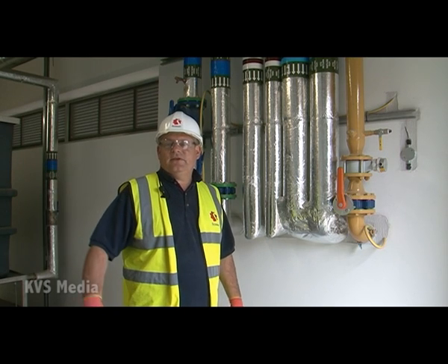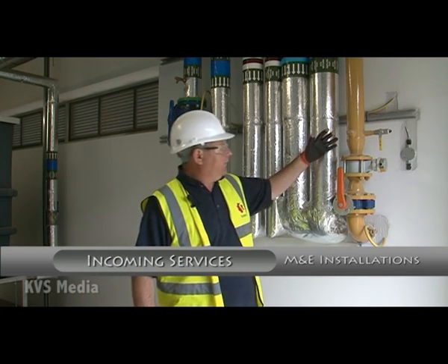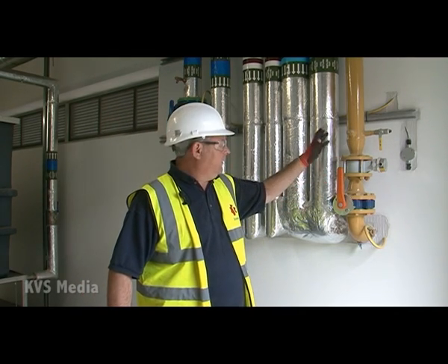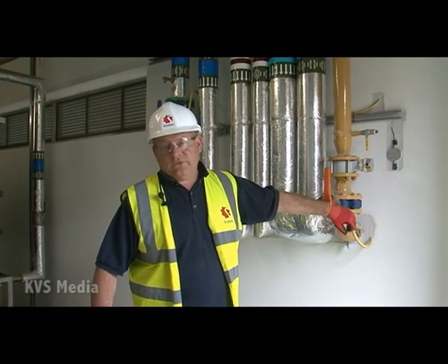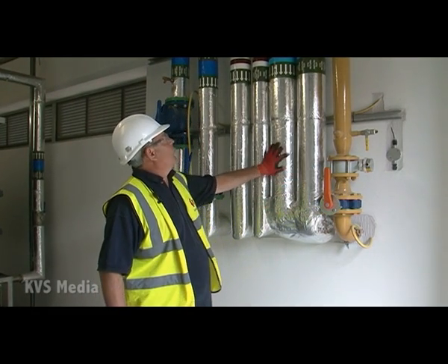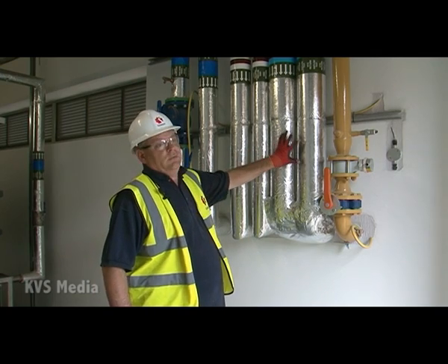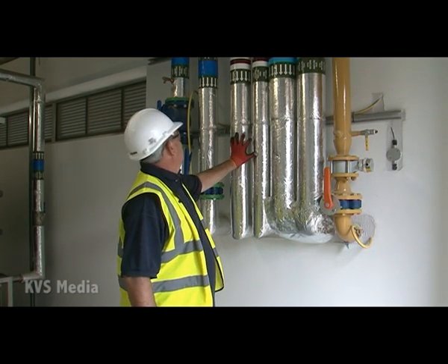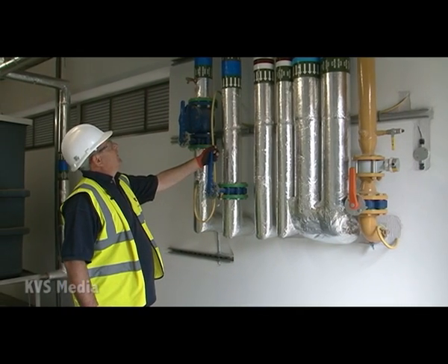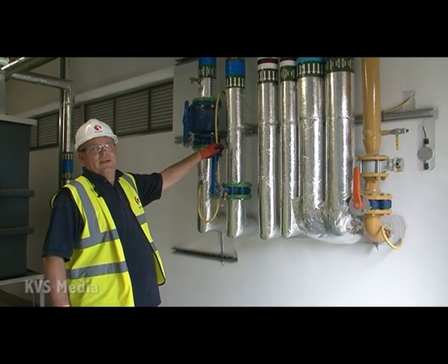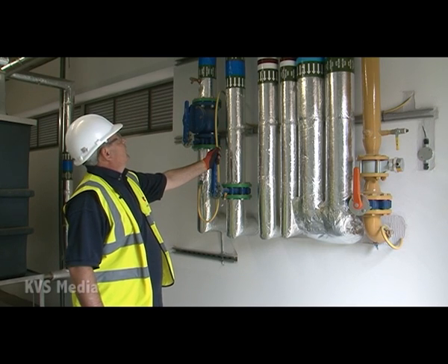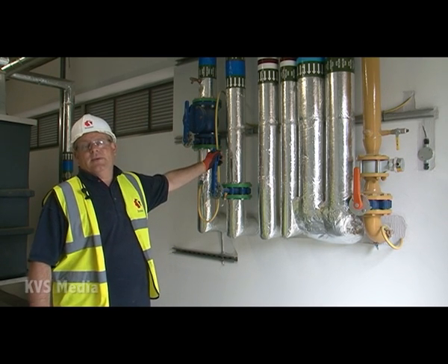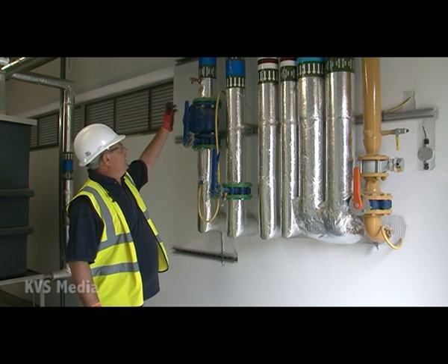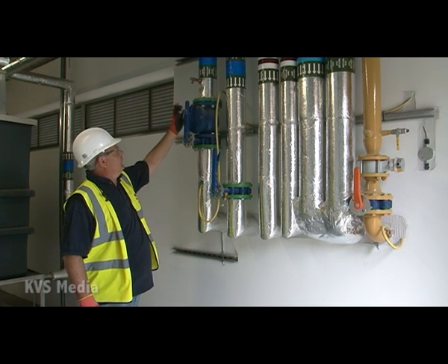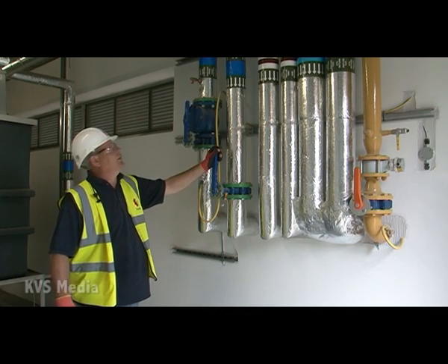We're now in the tank room, which is situated to the left-hand side of the plant room. I'll start going through some of the valves. Basically, we have the main incoming gas valve, which to isolate is just a pull and push down to close. We then have 4 sets of heating pipes. 2 do block A, 2 do block B. We then go through to the cold water mains. This is the outgoing from the tank through to the blocks A, B, C and D. This is the main incoming water main from the road. Again, to shut it off, they both just pull the levers down and down.